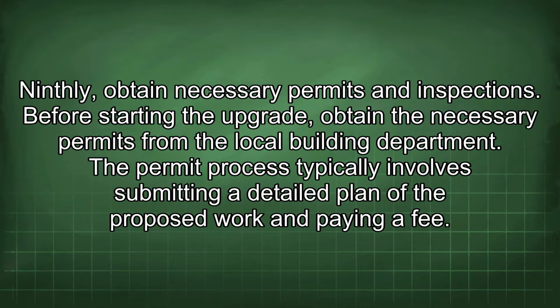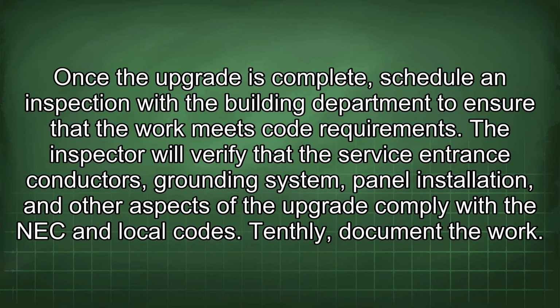Ninthly, obtain necessary permits and inspections. Before starting the upgrade, obtain the necessary permits from the local building department. The permit process typically involves submitting a detailed plan of the proposed work and paying a fee. Once the upgrade is complete, schedule an inspection with the building department to ensure that the work meets code requirements. The inspector will verify that the service entrance conductors, grounding system, panel installation, and other aspects of the upgrade comply with the NEC and local codes.